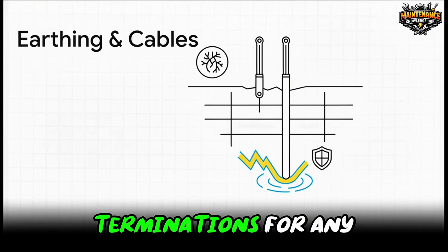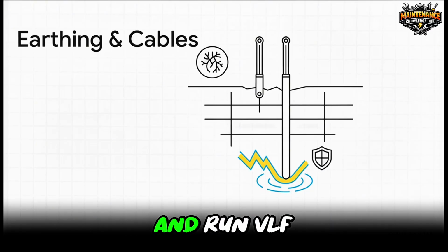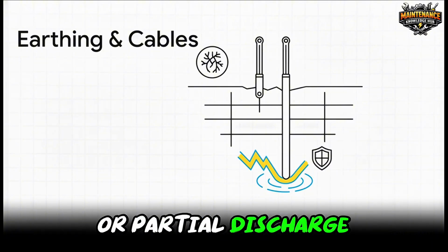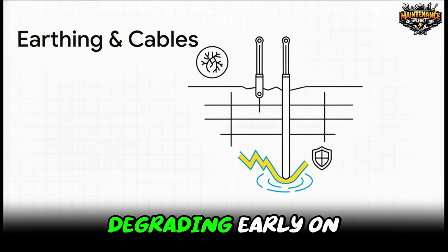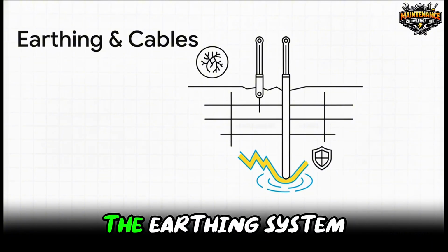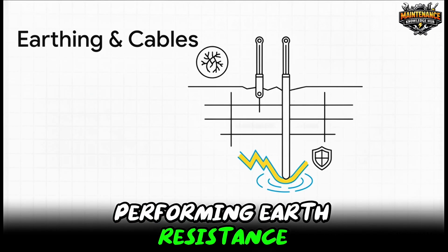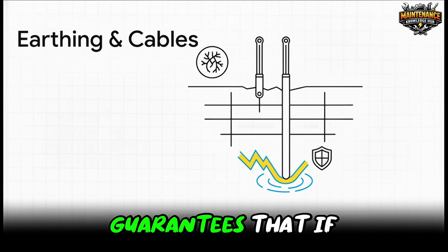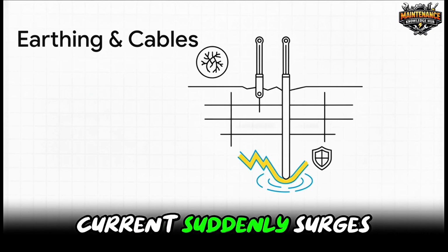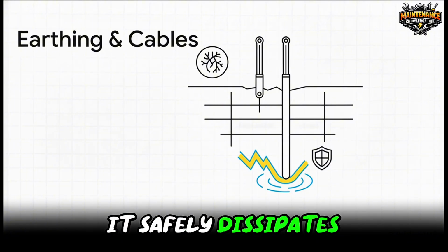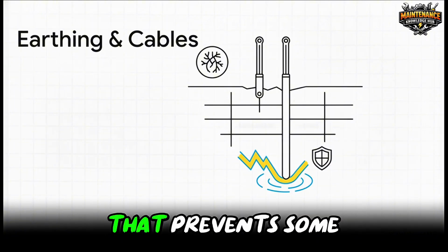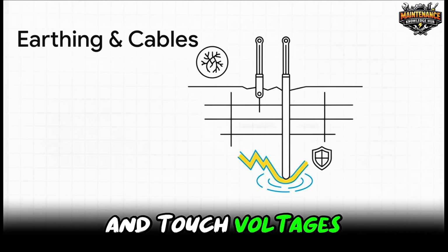We inspect cable terminations for any moisture ingress and run VLF or partial discharge tests to catch insulation degrading early on. Equally crucial is the earthing system. Performing earth resistance and continuity tests guarantees that if a massive fault current suddenly surges through the station, it safely dissipates right into the ground. That prevents some very lethal step-and-touch voltages.